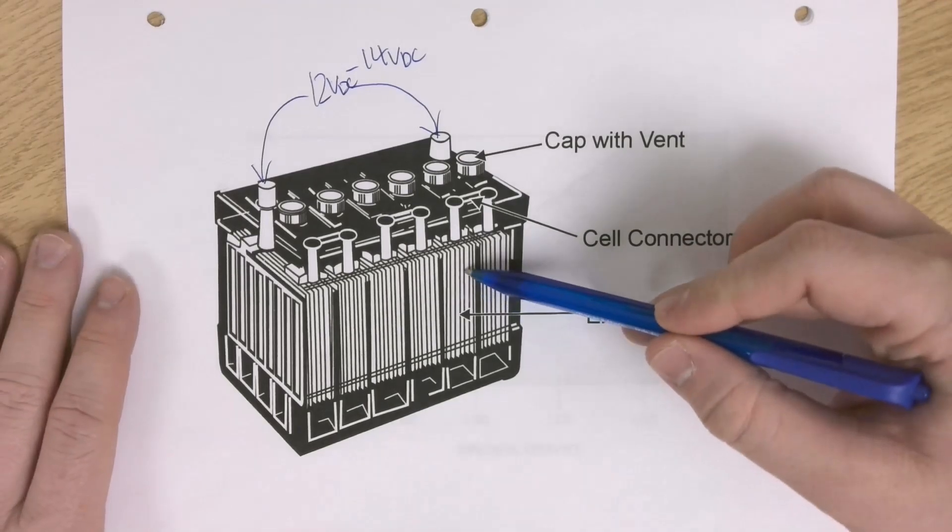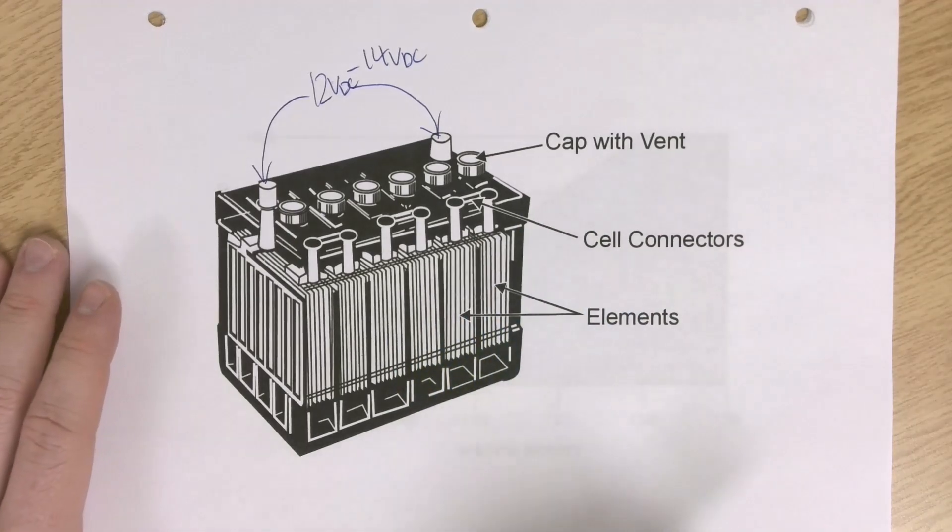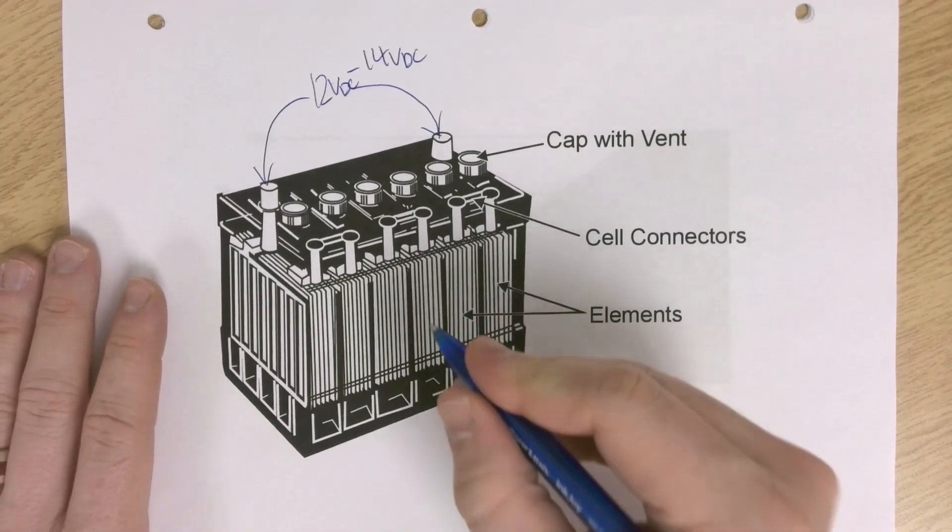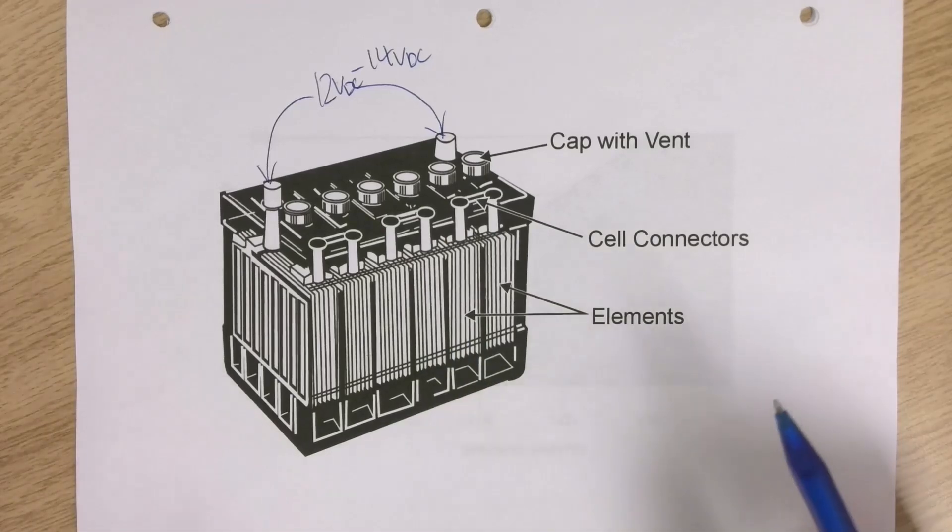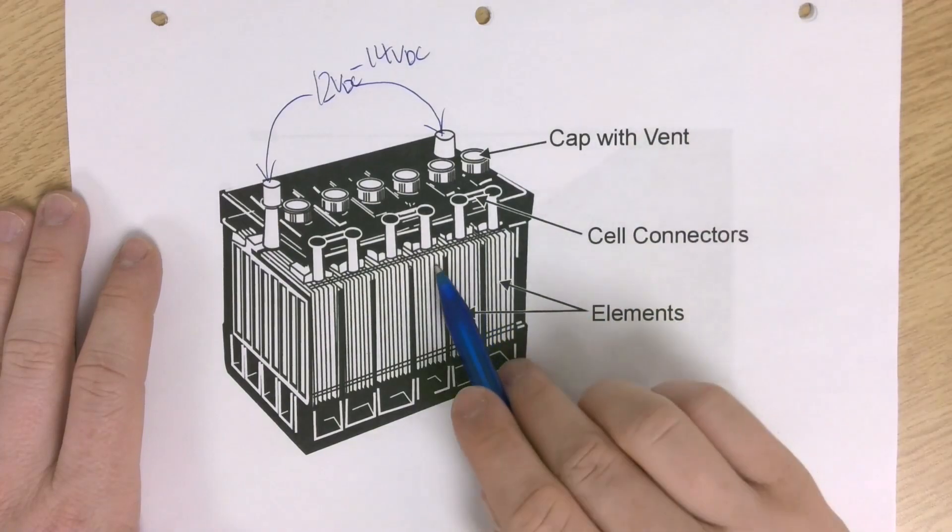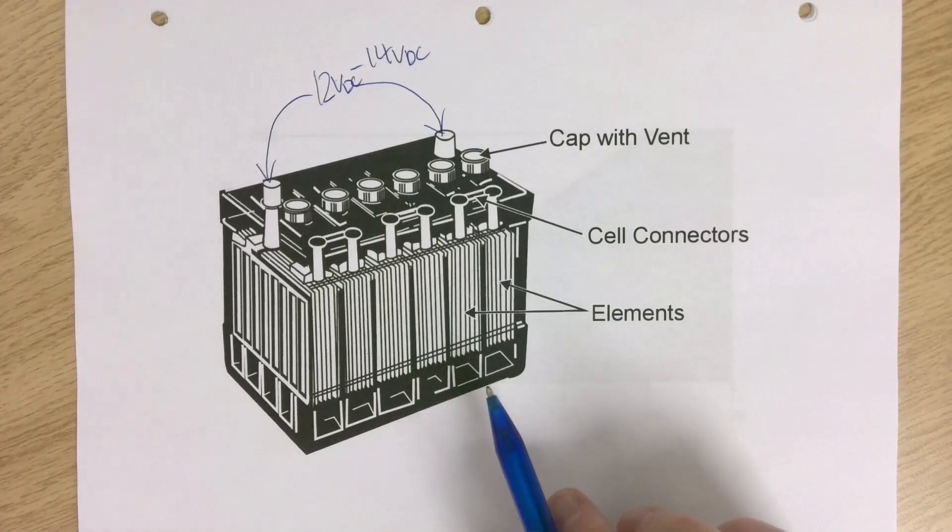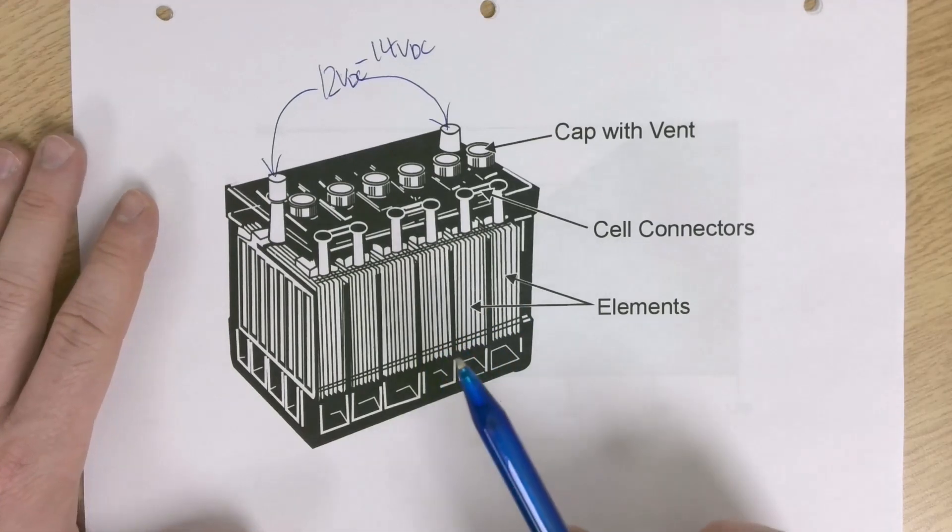Here we have our basic car battery. There's caps with vents, so someone's going to be able to maintain these batteries. They're going to be able to check the specific gravity, which is a term we talk about for flooded cell lead acid batteries. One of the problems with this flooded cell lead acid battery is it requires some maintenance. The electrolyte that facilitates the chemical reaction becomes basically water. The right balance of acid and water is what is required for this type of battery. This is a very common type of battery. It's relatively cheap, and it's in pretty much every car, or at least every combustion engine car. These are also used in forklifts, in scissor lifts.